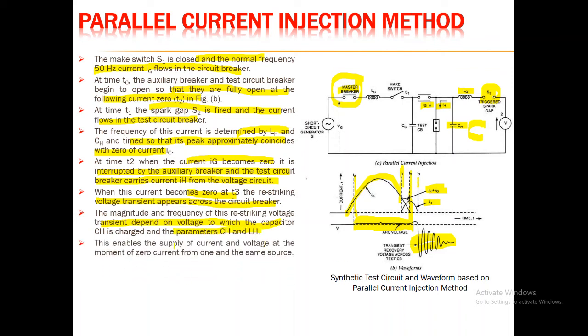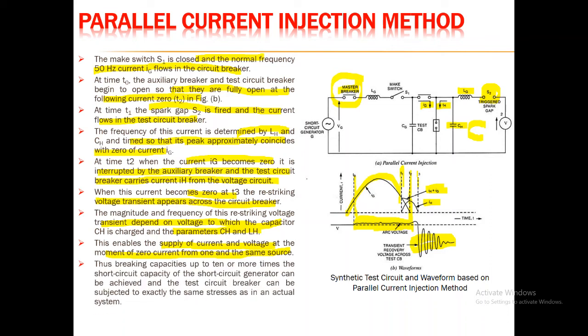The magnitude and frequency of this restriking voltage during the transient stage can be calculated from the values of CH and LH. This enables the supply of current and voltage at the moment of zero current from one and the same source. The breaking capacity of up to 10 or more times the short circuit capacity of the generator can be achieved, and the test circuit breaker can be subjected to exactly the same stress as in an actual system.